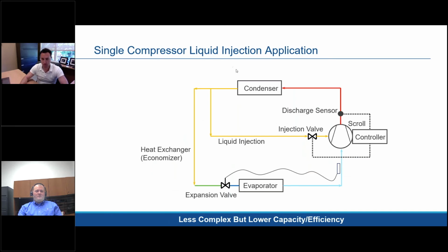And here's an example of liquid injection. As I said earlier, it's a little bit more of a simple system, so you don't have the economizer or heat exchanger. You don't have the expansion valve on that line. All you have is fluid coming from that liquid line, coming back to the compressor itself. And then there's a controller typically built onto the compressor, which is going to control how much liquid injection is needed in that compressor in order to keep it cool. And there's usually a discharge sensor required as well on the system.